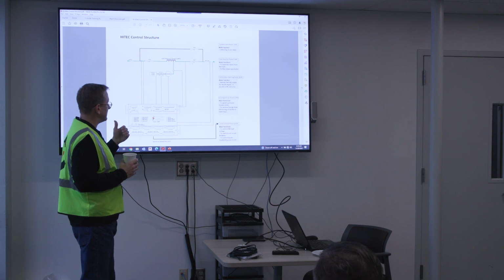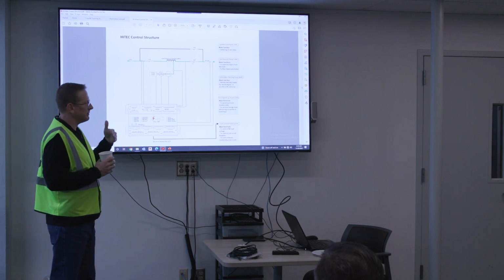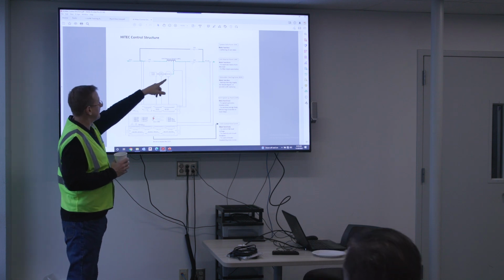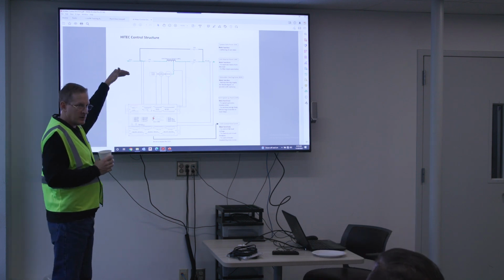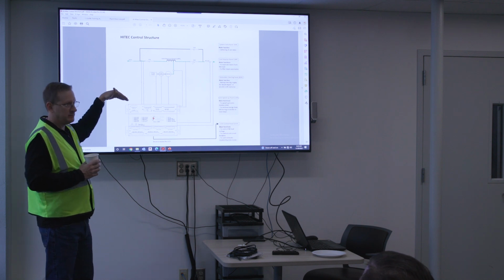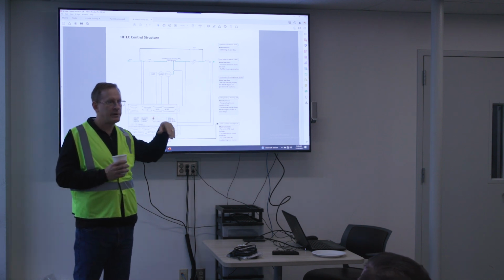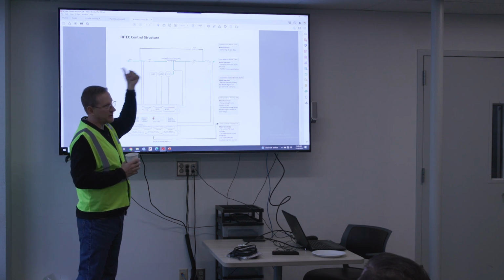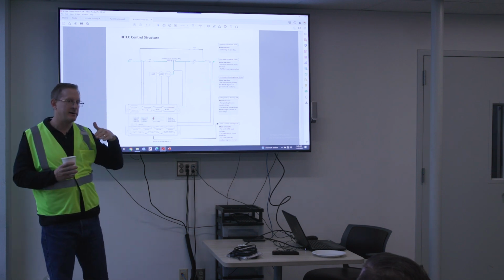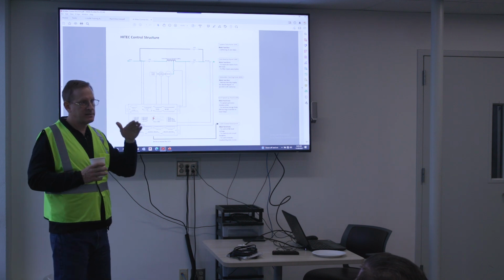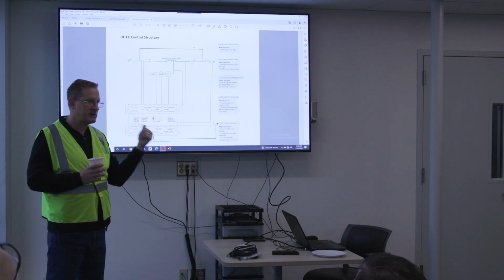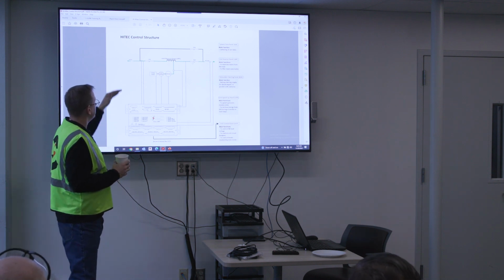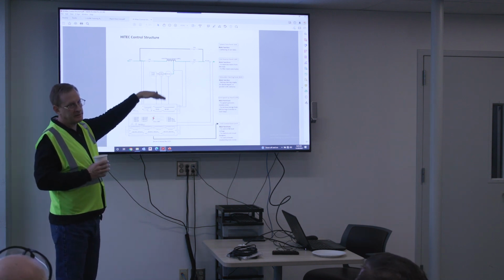Because one thing that will actually happen if we're running at a reduced load voltage is if we stay at 4160 on the output and your load voltage is at a lower level, 5% lower or whatever, we'll actually export some vars back into the utility because our voltage is higher. And that's not necessarily a bad thing, but it does provide some extra current back into the utility, which is reactive current, that we can mitigate if we lower our voltage a little bit on the output side.